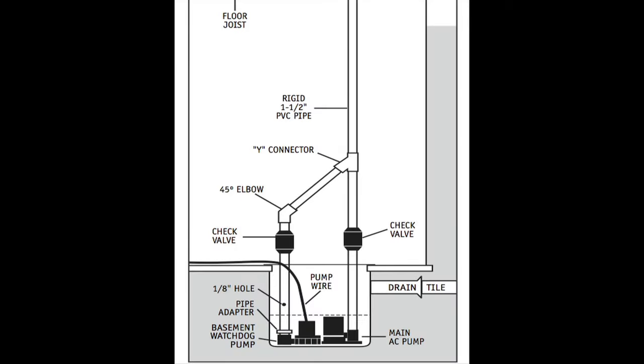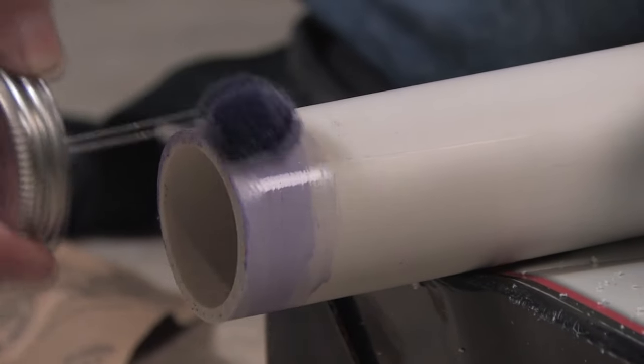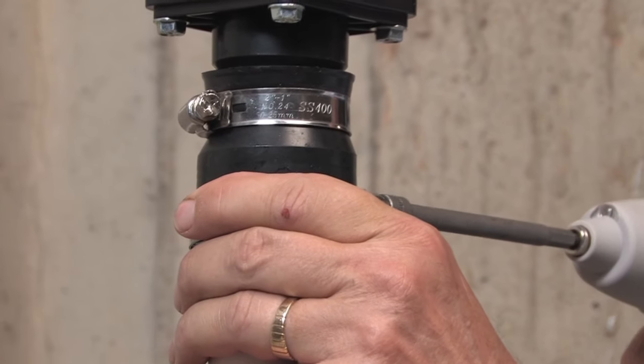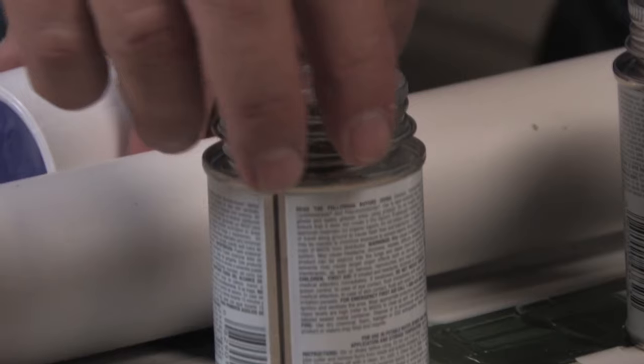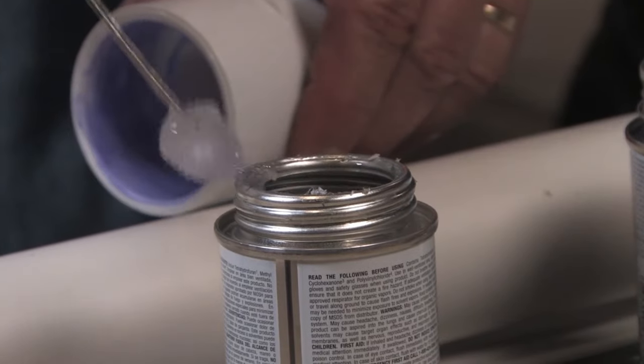The pipes are the correct length when the discharge pipes on both pumps are parallel and both pumps rest on the floor of the sump pit. Once the assembly is correct, take the pieces apart, prime and cement all the connections, and tighten the hose clamps on the check valves. See the video segment on cutting and gluing pipe if you're not familiar with the process.